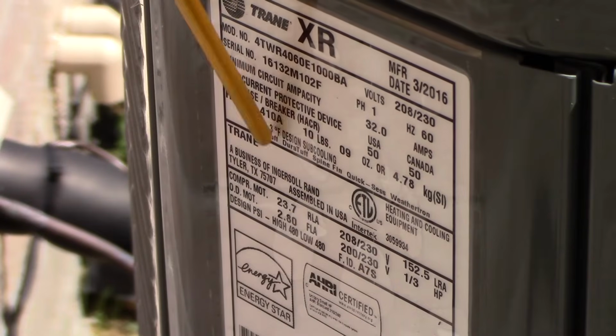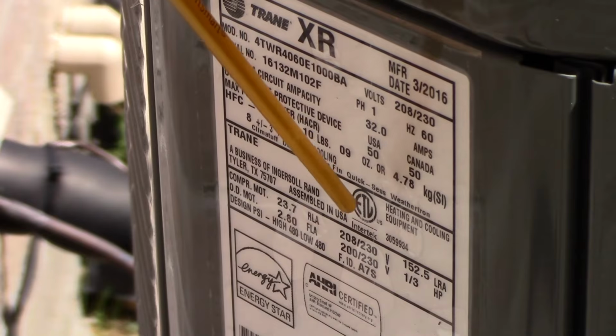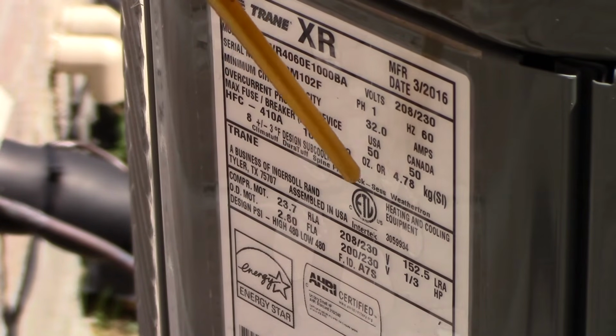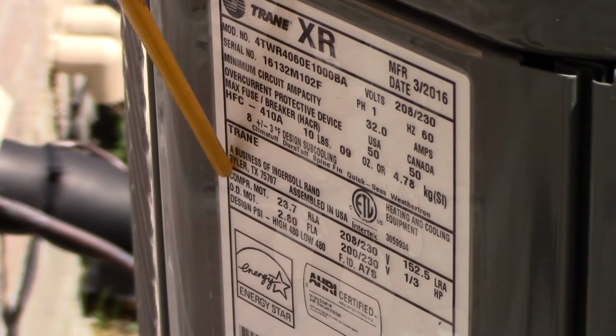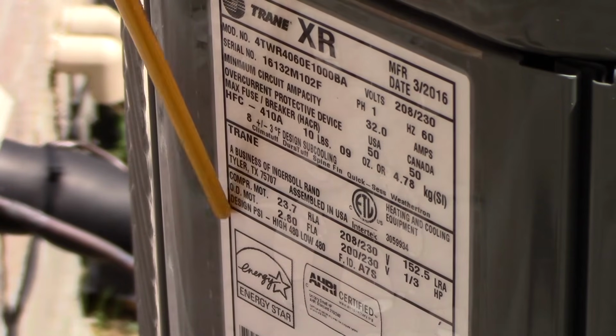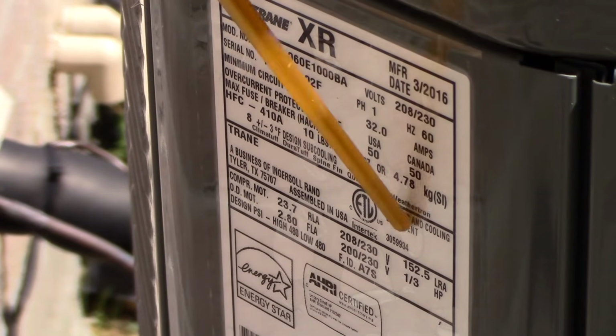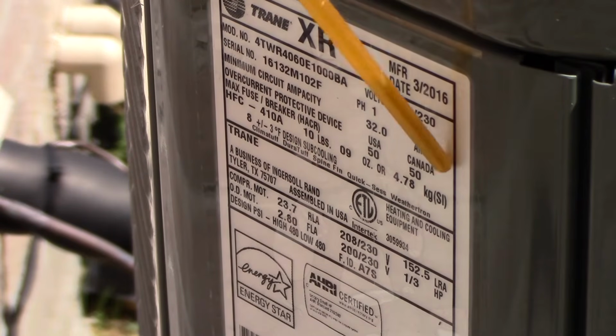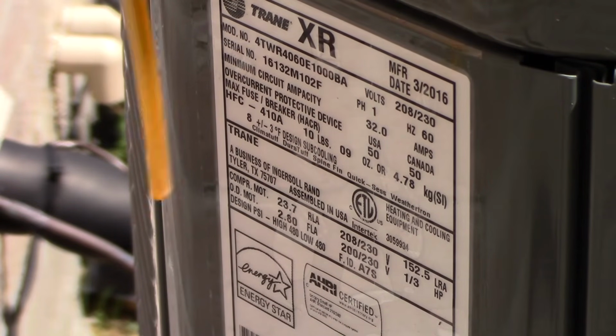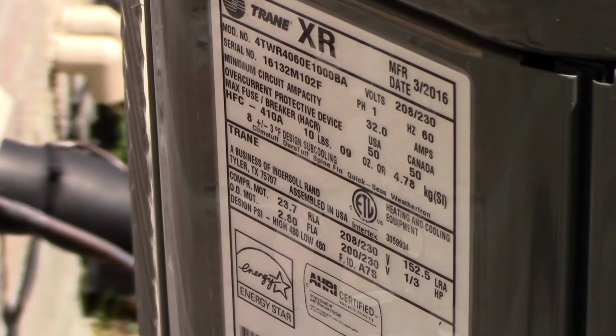So this is what you follow to make sure that's what's installed inside your panel. In that way, if you have a breaker on a conductor that looks like it's too small, and it's on something like this outdoor unit or an indoor air handler unit, you go and look at the nameplate and you'll see that it is okay. This is acceptable and is allowed in the National Electrical Code. There's an initial startup surge and then it comes down to normal running current. So if you follow this minimum and maximum as put on the label, then you shouldn't have any problem, and that kind of gives you an idea of why that breaker might be larger when it's terminated onto a smaller conductor in the panel.